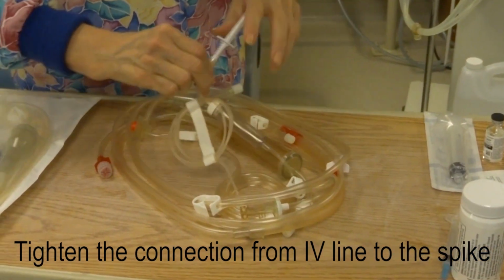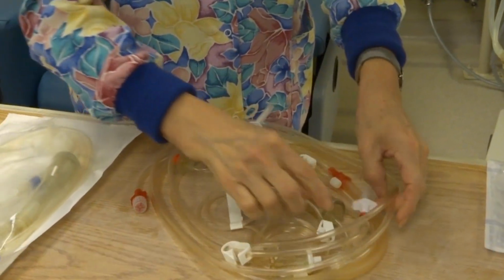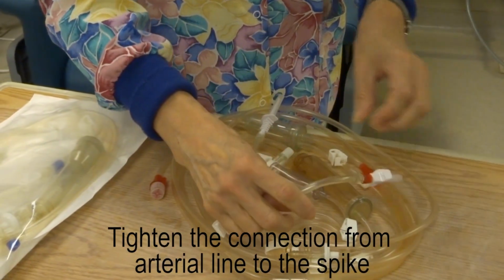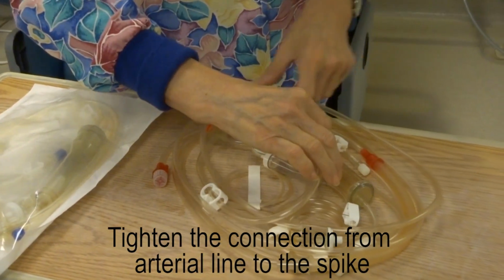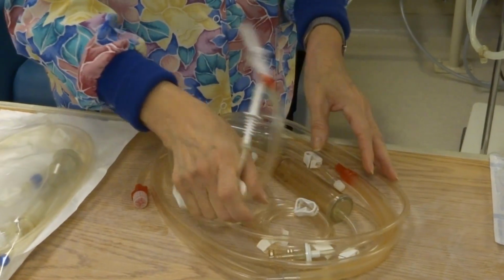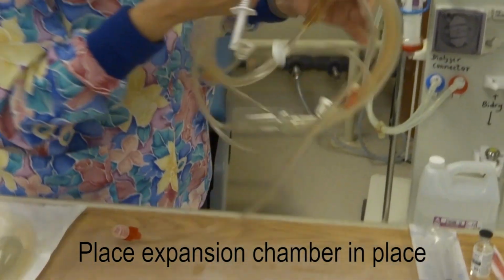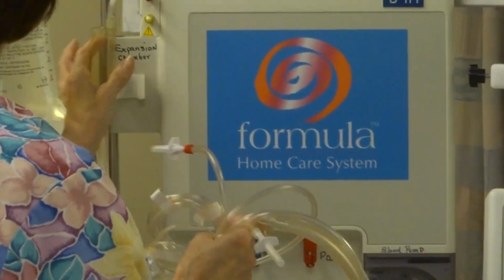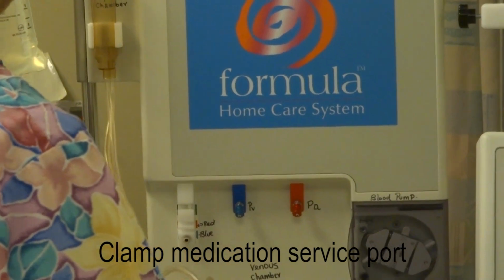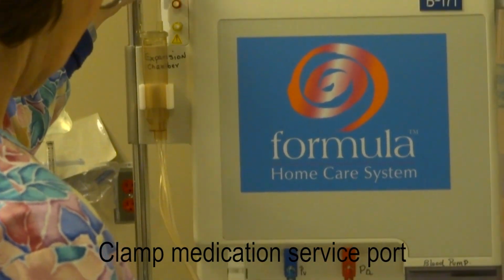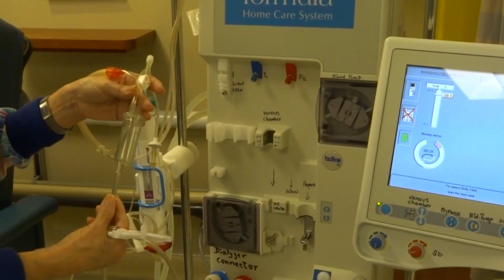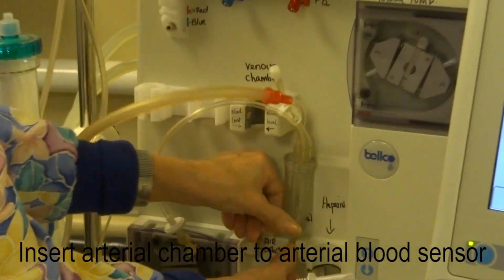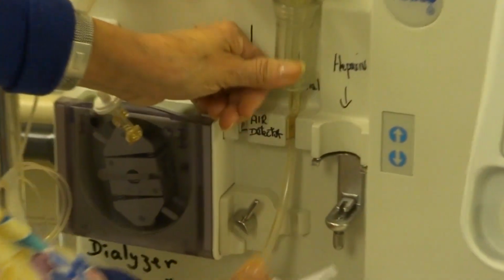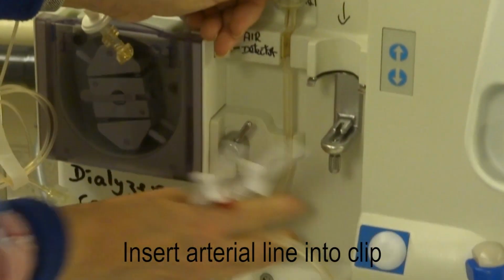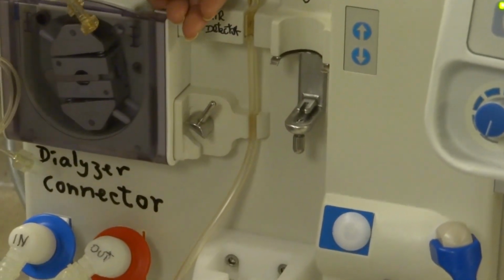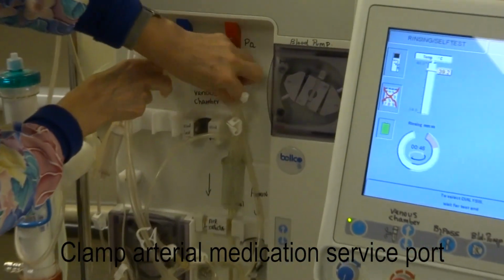Tighten the connection of the IV line to the spike. And tighten the connection of the arterial line to the spike. Place the expansion chamber in its support at the top left of the machine. Close the medication service port at the top of the expansion chamber. Insert the arterial chamber into the arterial blood sensor. Insert the arterial line into the clip below the blood sensor. Clamp the arterial medication service port.